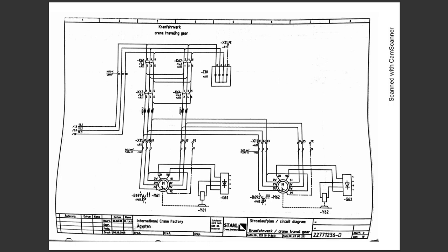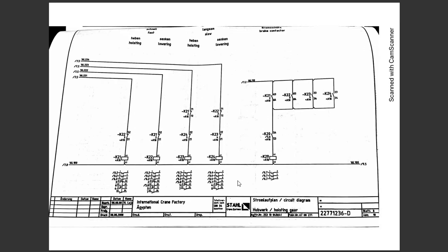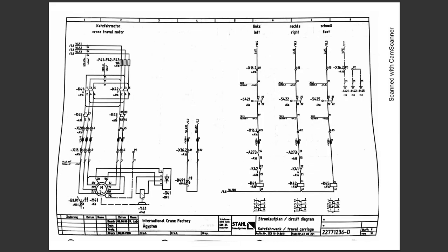make this motor stop instantaneously and not move with the inertia, because the inertia here is forbidden inside overhead cranes. We can't move by inertia, because if I want to stop this motor, I want it to stop instantaneously. If it's moving, it will not be safe. So for safety, we must make the motors stop instantaneously. So each motor of those and the motor of the lowering also have a mechanical clutch or braking inside the motor. And also here we have a mechanical braking inside, or internal, for the motor.